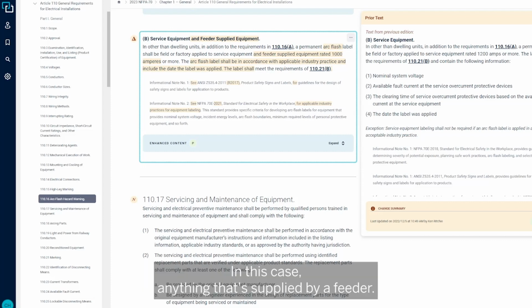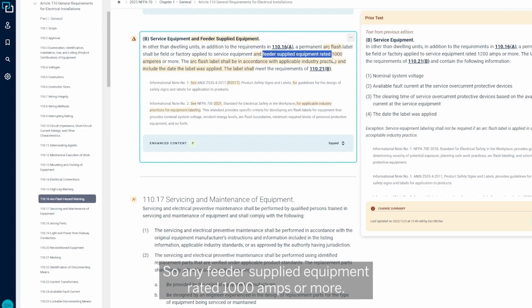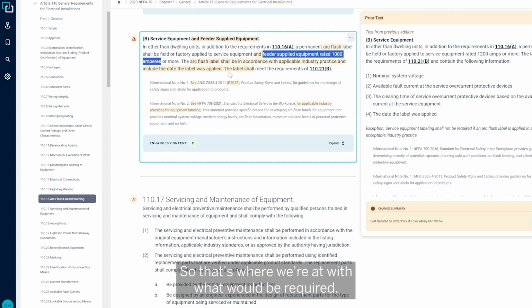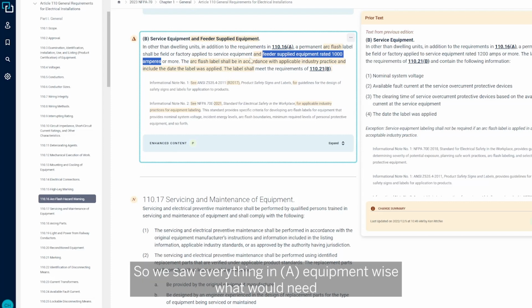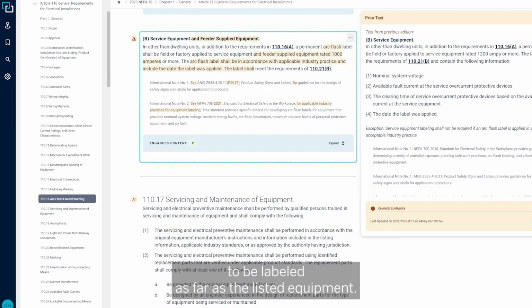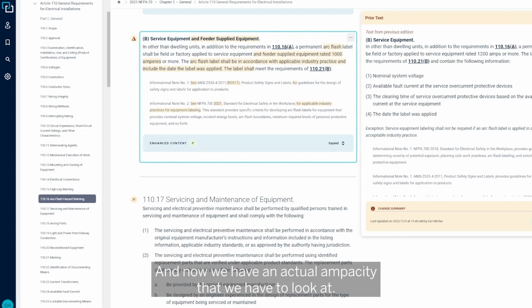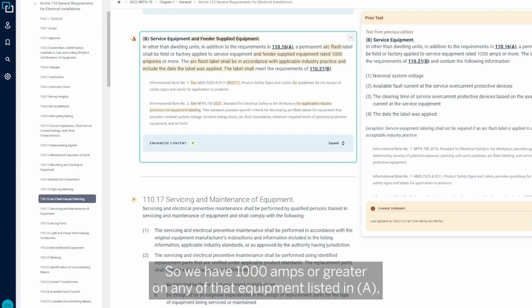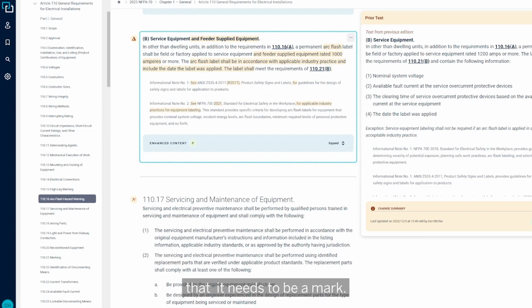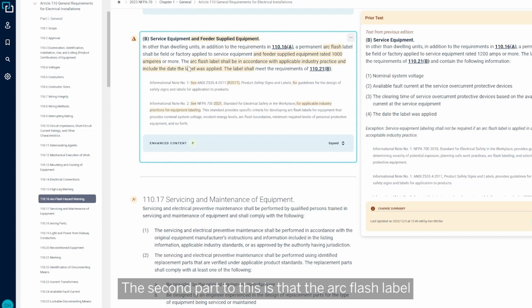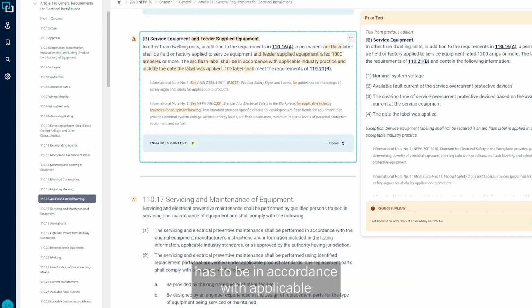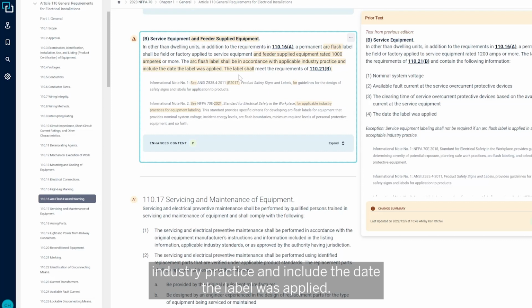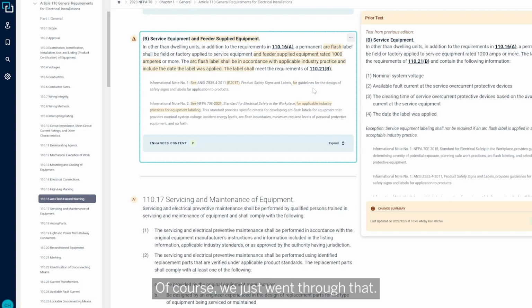In this case, anything that's supplied by a feeder, and now the ampacity has changed from 1200 to 1000. So any feeder supplied equipment rated 1000 amps or more. So that's where we're at with what would be required. So we saw everything in A, equipment wise, what would need to be labeled as far as the listed equipment. And now we have an actual ampacity that we have to look at. So if we have 1000 amps or greater on any of that equipment listed in A, then it needs to be marked. Second part to this is that the arc flash label has to be in accordance with applicable industry practice and include the date the label was applied. And then we see that 110.21(B) is mentioned again. Of course, we just went through that, but it would apply here as well.